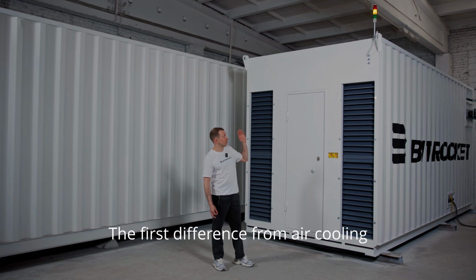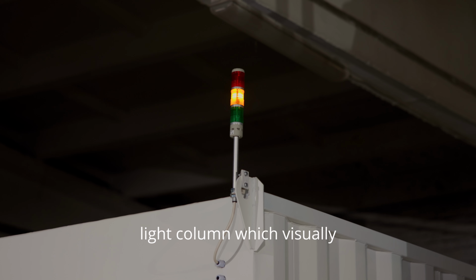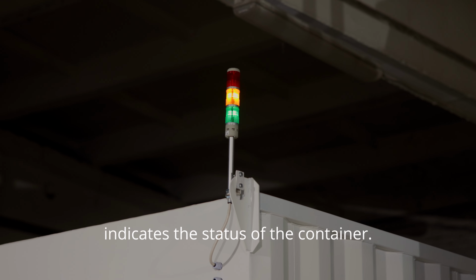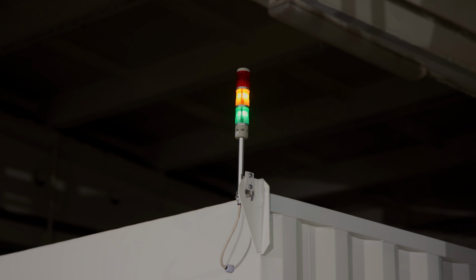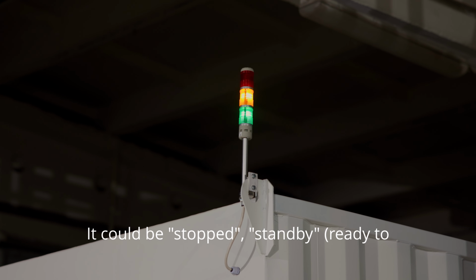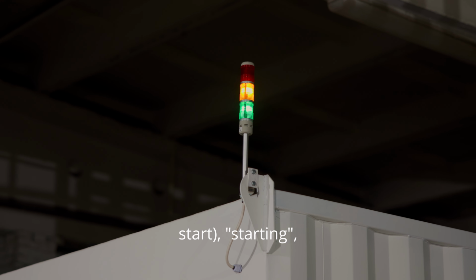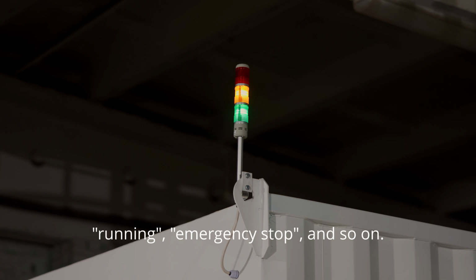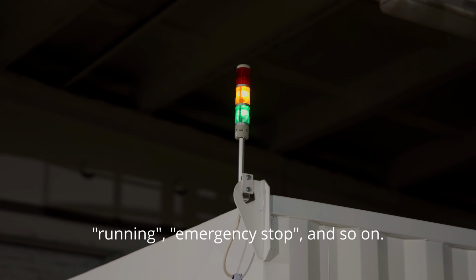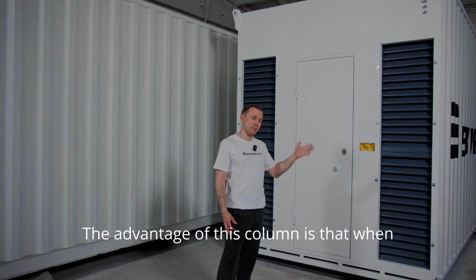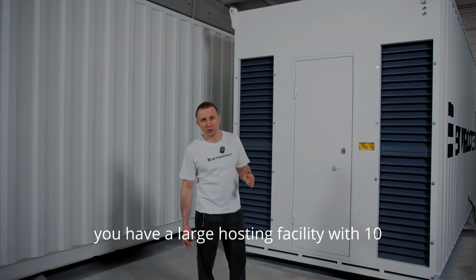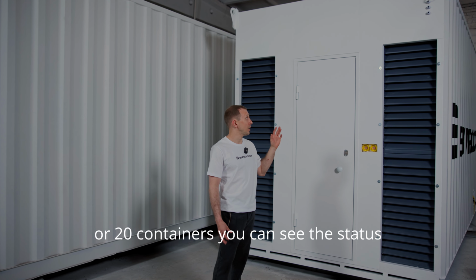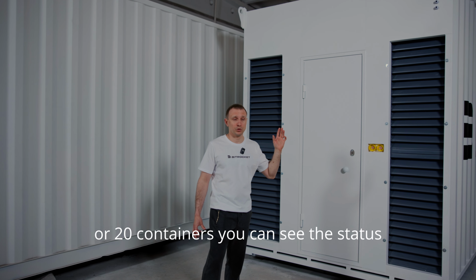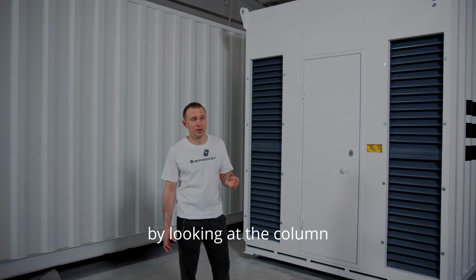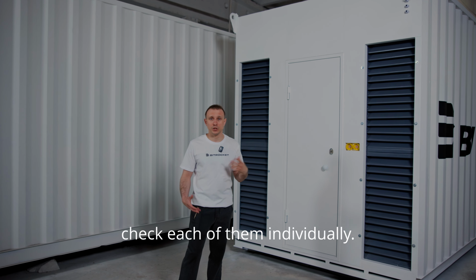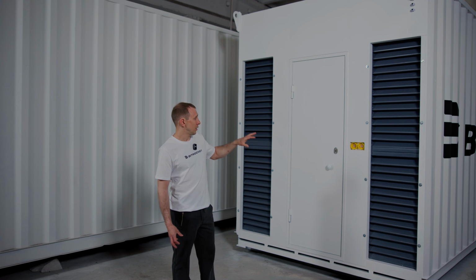The first difference from air cooling containers is the status light column, which visually indicates the status of the container. It could be stopped, standby, ready to start, starting, running, emergency stop, and so on. The advantage of this column is that when you have a large hosting facility with 10 or 20 containers, you can see the status of each of them simply by looking at the column without having to go and check each of them individually.